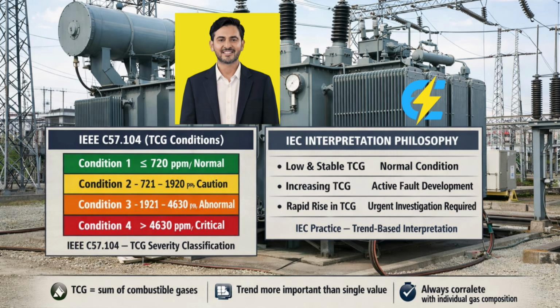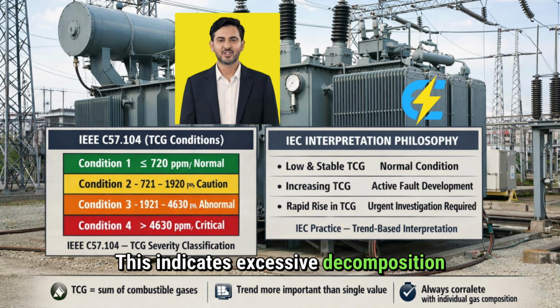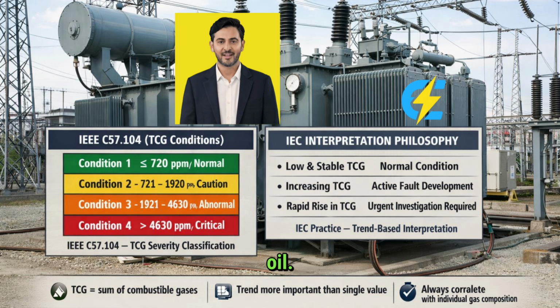Condition 4 is the severe range, with TCG above 4630 parts per million. This indicates excessive decomposition of cellulose insulation or oil. The standard clearly states that continued operation could result in failure of the transformer. This is your red light. Immediate action is required and you should be preparing for an emergency outage.